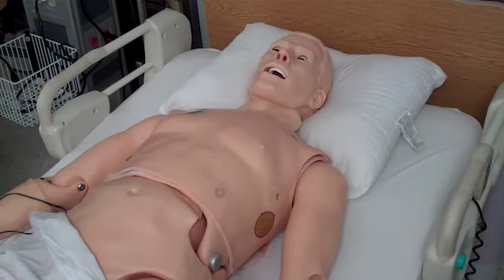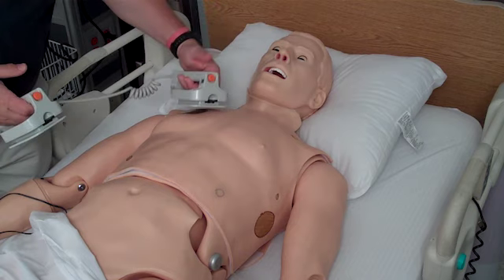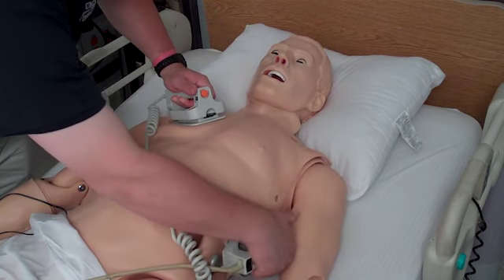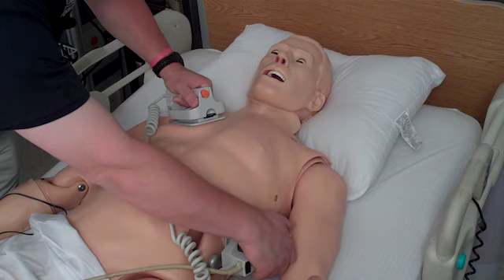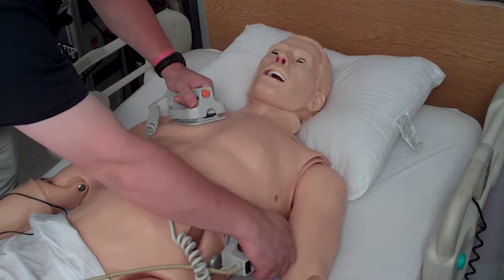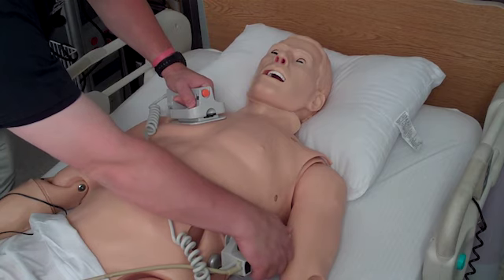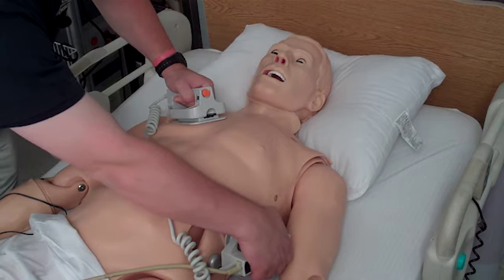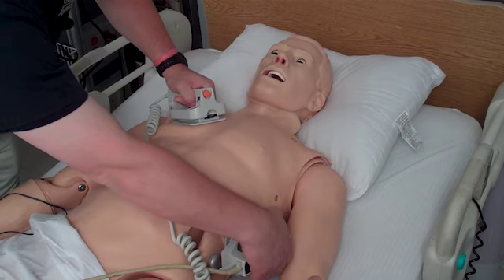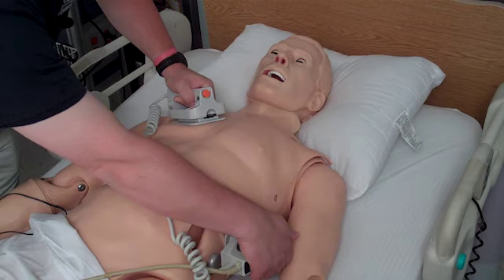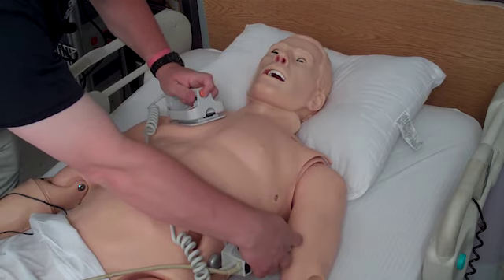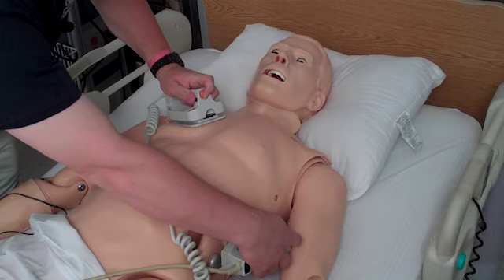When using the paddles, after applying a small amount of conduction jelly, place your sternum paddle and your apex paddle on the mannequin. Should you require a change in the energy setting, the buttons on the left paddle can be used to do that. Once you're at the proper energy setting, press the charge button on the right paddle to charge. Once the defibrillator is set and charged, clear the patient, and then press both orange buttons simultaneously to deliver the shock.